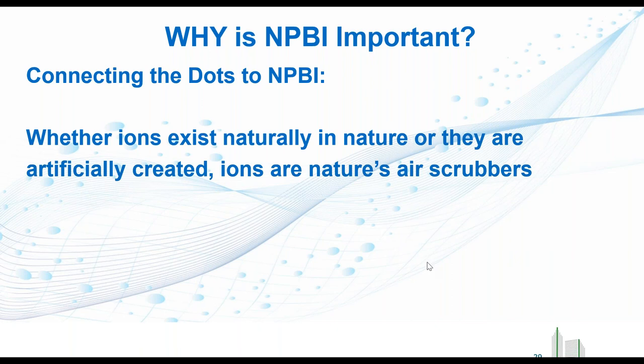Before we jump into the next slide, April mentioned as part of the Harvard studies that one of the recommendations that is being made is increase the filter efficiency in your HVAC systems to pick up more particulate matter. That works great in some systems, but some HVAC systems are not designed so that they can handle a filter with a greater pressure drop across it. So let's talk about how needlepoint bipolar ionization works.